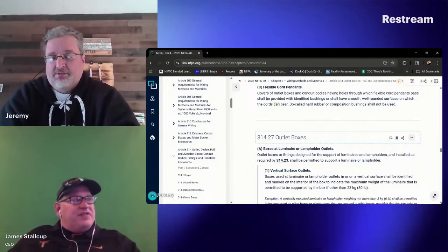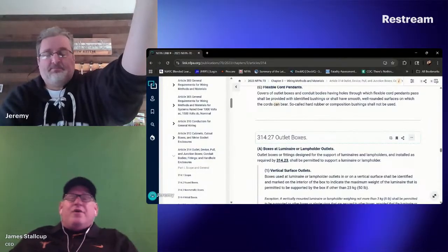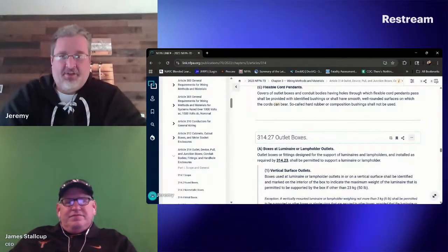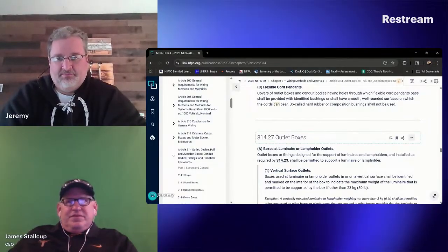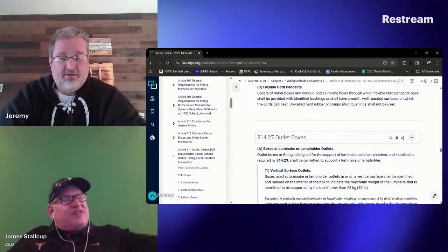Branch circuit is what comes over to the switch. That's your branch circuit, and then after that, you're going over feeding whatever it is you're going to feed. Okay. What are those conductors called then? They're just conductors going over. They're terminations. It'd be no different. They're not branch circuit conductors? The branch circuit conductors is what is sized.